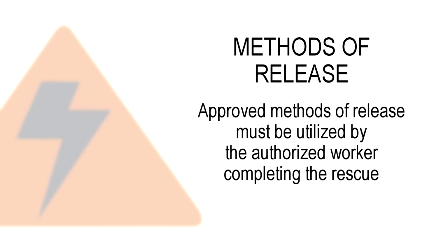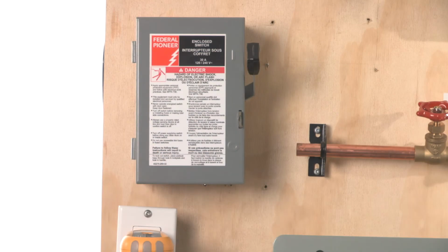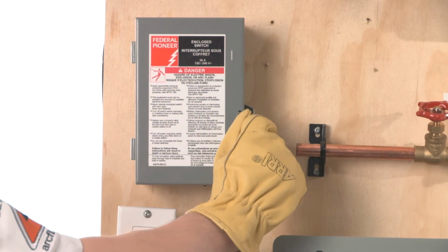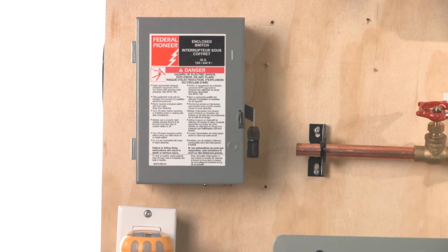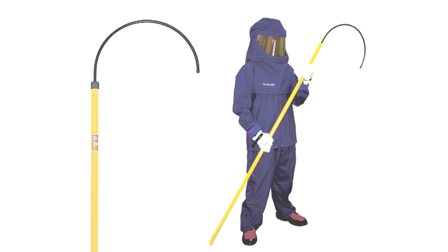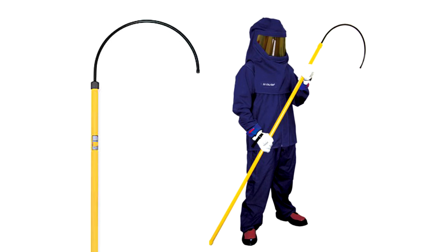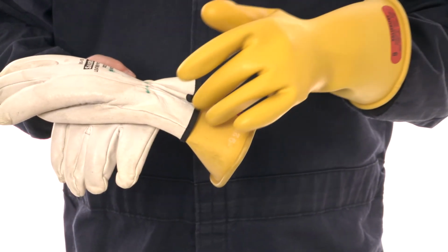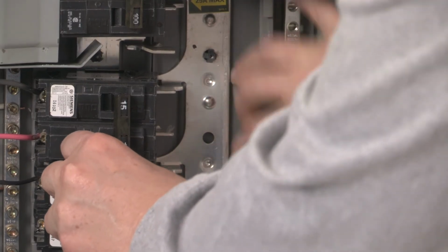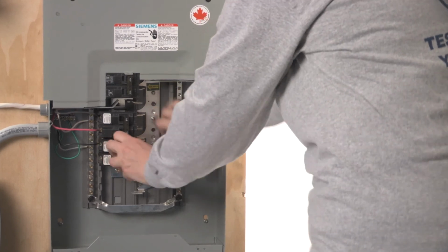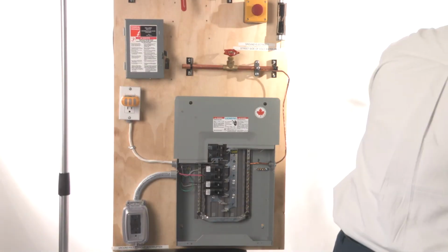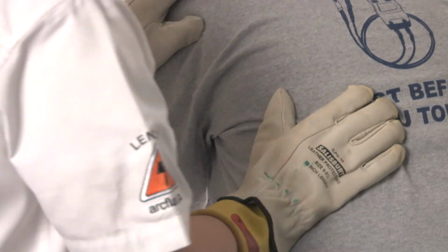Methods of release: approved methods of release must be utilized by the authorized worker completing the rescue. The three methods available are: turn off the power by identifying the circuit breaker or disconnect switch and placing it in the off position; rescue the victim using a hot stick, if one is available; or use rubber insulating gloves with leather protectors, ensuring that the rescuer's body does not make contact with the victim, only the hands.